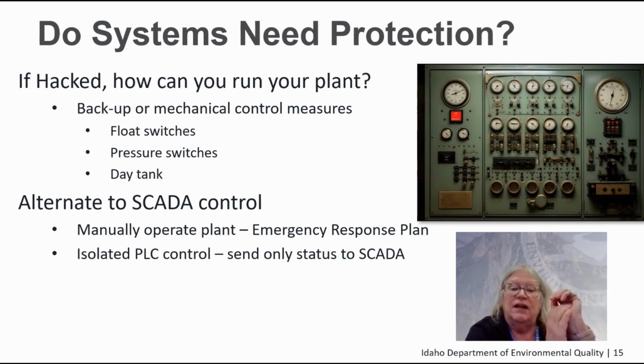Another option: if you really need a PLC to control a system, you could have it as an isolated PLC with its own internal network, not connected to SCADA for control. It would only send status and alarms to SCADA — SCADA does not control it.